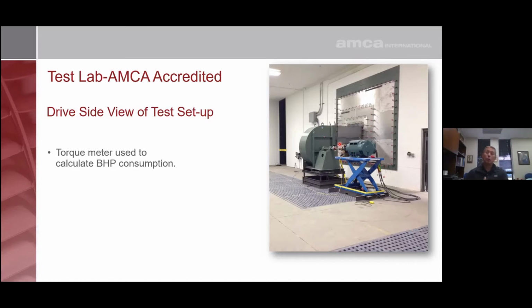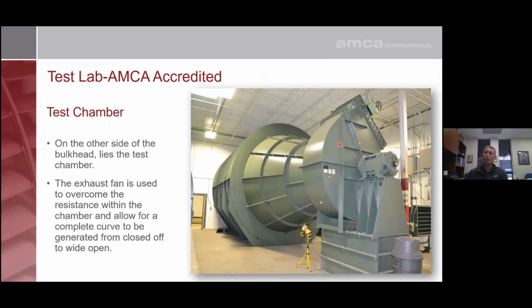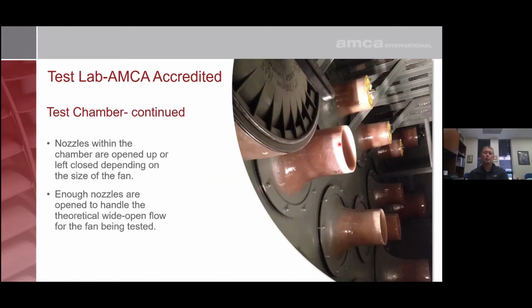Behind that bulkhead, where the fan is blowing through that ductwork system, is a large test chamber. And within the test chamber is a series of nozzles. And those nozzles are specifically how we calibrate that chamber for the fan that's being tested. If we have a little fan that's being tested here, most of those nozzles are going to be open, or excuse me, closed. If we have a large fan, all these nozzles will be open. So we'll remove the caps off of these nozzles and allow more air to flow through that system.